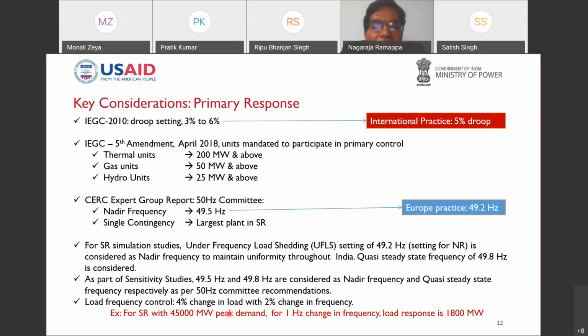Load frequency control, that is 4% change in the load with 2% change in frequency. In fact, we call it the power number. In the Indian context, in most of the load dispatch centers, we use the terminology power number. Therefore, for the southern region with 45,000 megawatt of peak demand, for 1 Hertz change in the frequency, the load response is about 1,800 megawatt. Therefore, the power number we have considered in the simulation is 1,800 megawatt.